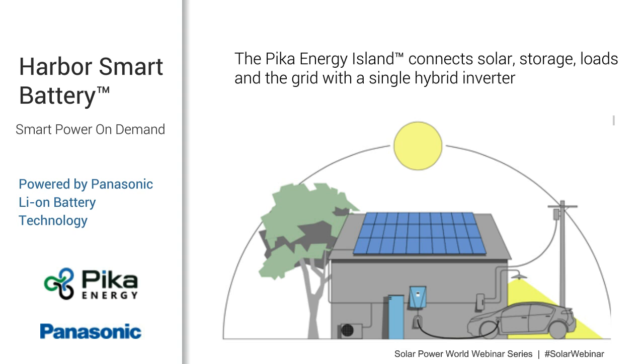So you can see in the photo here, this is an image showing how you have a DC bus integrating your PV and your battery on the DC side, and then on the AC side, you've got your loads, including EV or HVAC. You can also couple DC loads to the Pika Energy Island as well.